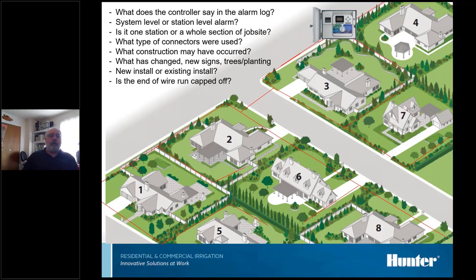I run into this often enough that I put this on here, and that's especially in phased communities, where it's real common and it's perfectly fine to run wire over to the next section to be done, and just leave it there till you come to that section. If you do that, then wires need to be capped off. If you don't, it's like an antenna waiting for a lightning strike to hit them wires. And they'll start corroding and causing problems otherwise too. And yeah, is there an as-built? If not, make your own.